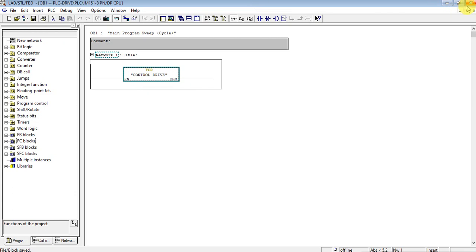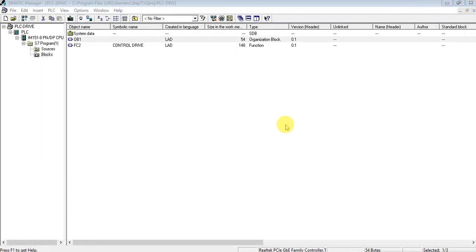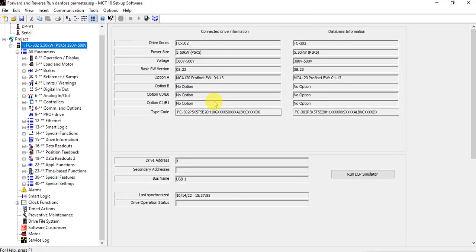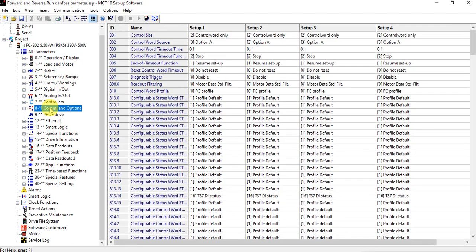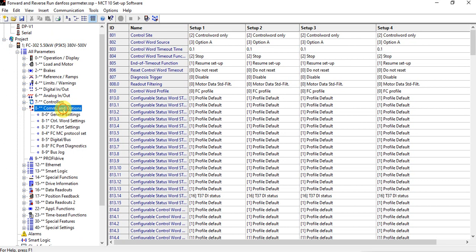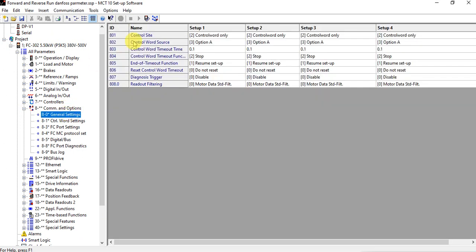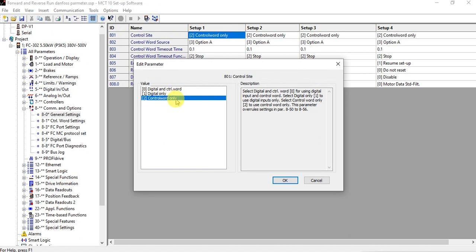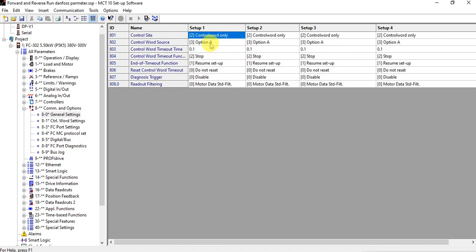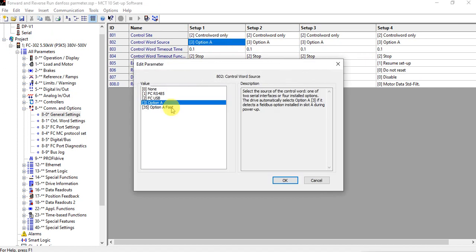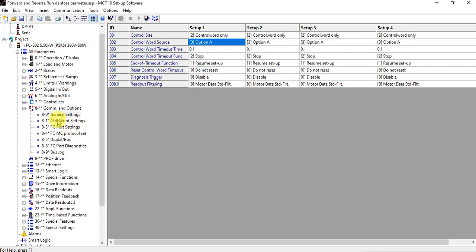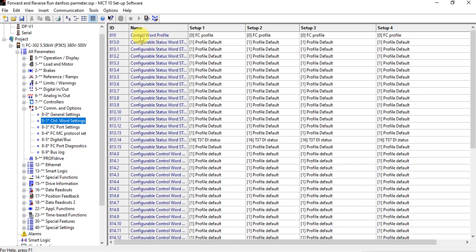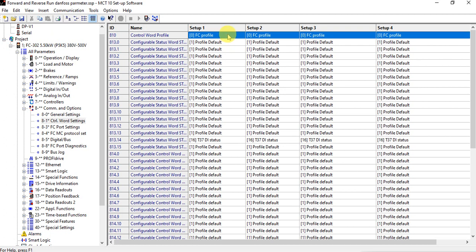Let's go to the MCT 10 software, which is the software for the Danfoss drive. We also have to change some important parameters on the drive using the local panel or MCT 10 and download them. The first important parameter is the control site — it must be set to control word only, or digital control word. We have to select 'control word only.' And here we have to also select option A. The second important parameter is the control word profile — it must be set to FC profile for Danfoss drives.